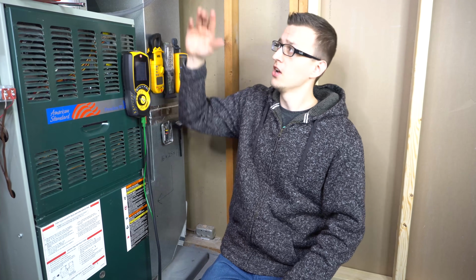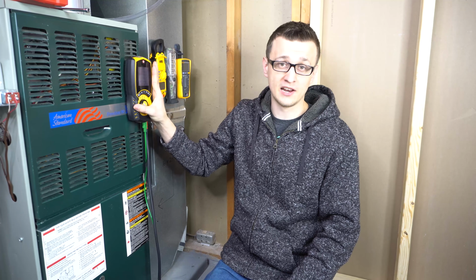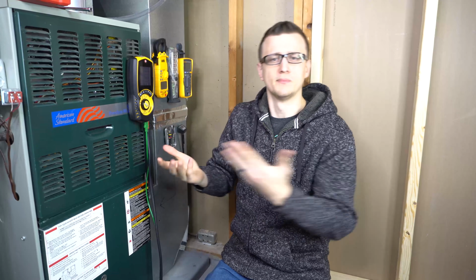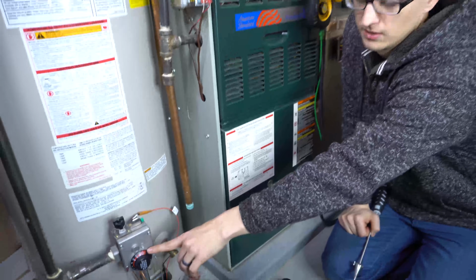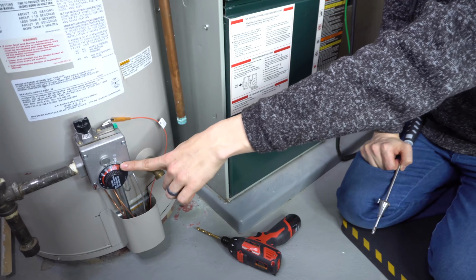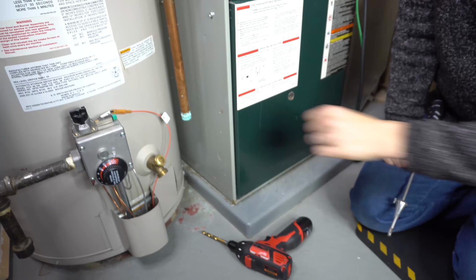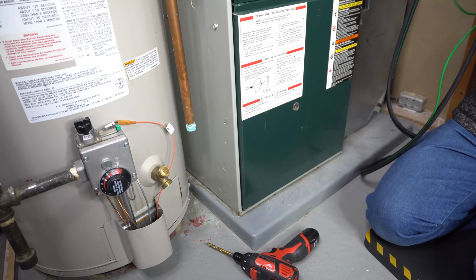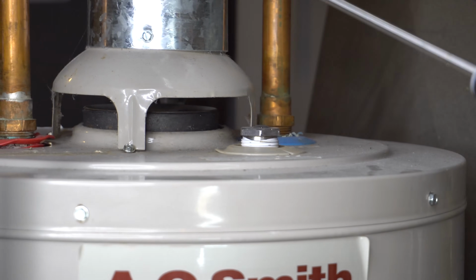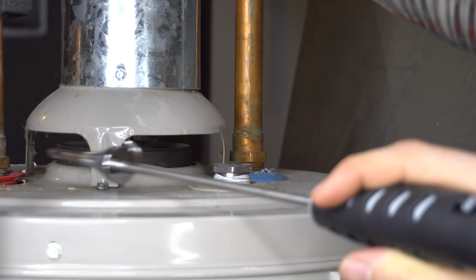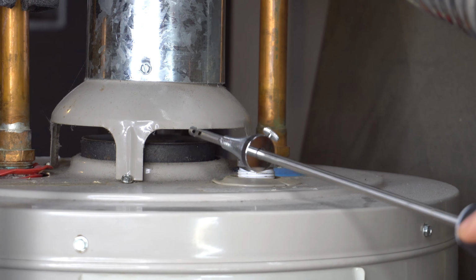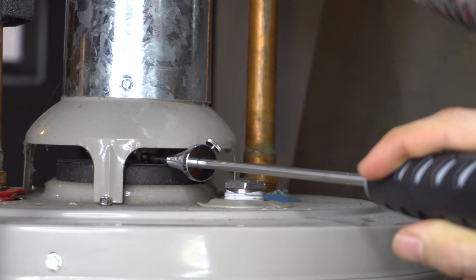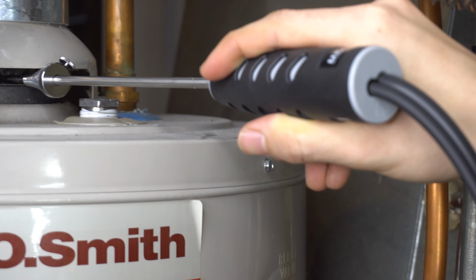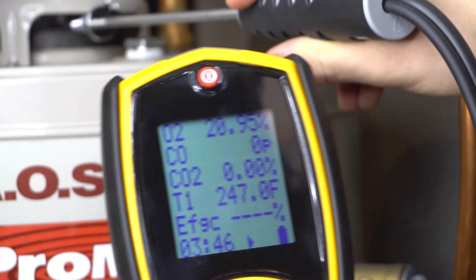Well guys, that is how to take the carbon monoxide reading along with other readings on the furnace flue using a combustion analyzer. And since there's a water heater right next to me, why not? Let's take some readings on that as well. I already have the temperature turned way up to very hot. That turned on the burner, and it's been on for about 2 or 3 minutes now. So we are ready to check what kind of emissions it is producing. Since this water heater is atmospheric draft, meaning it's pulling in oxygen just from the room, I don't have to drill any holes. I can just stick my probe right in the middle of that vent pipe or the flue and see what kind of readings I get.